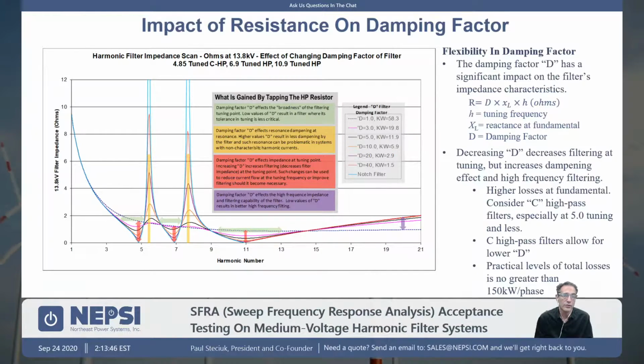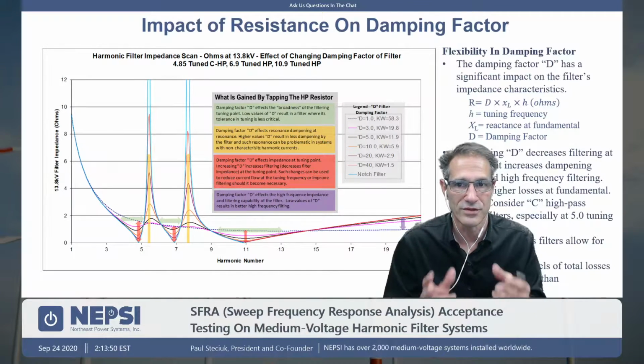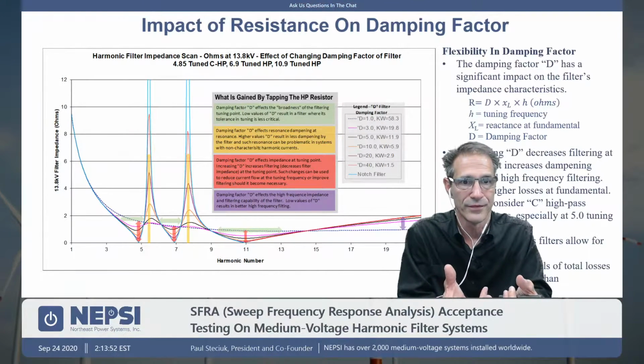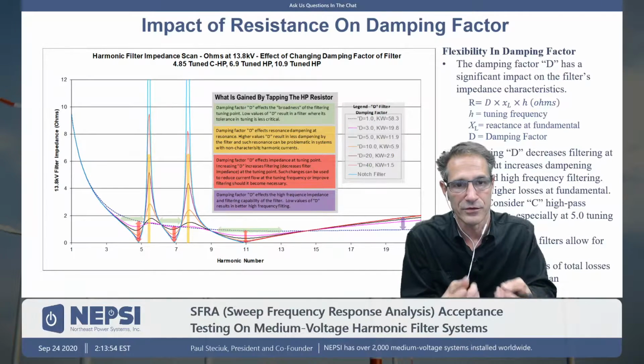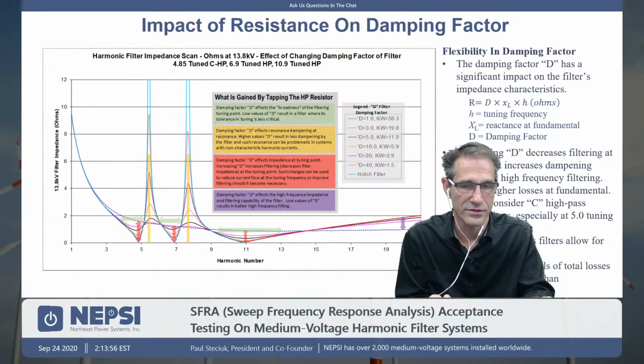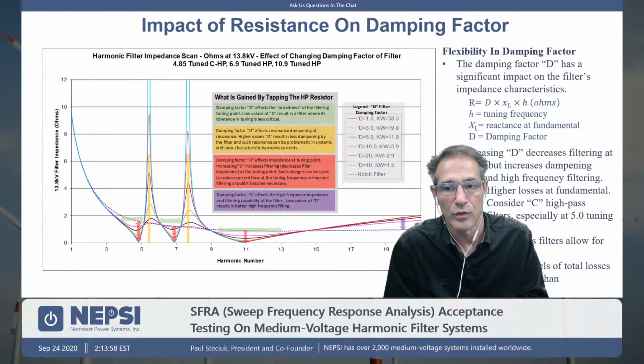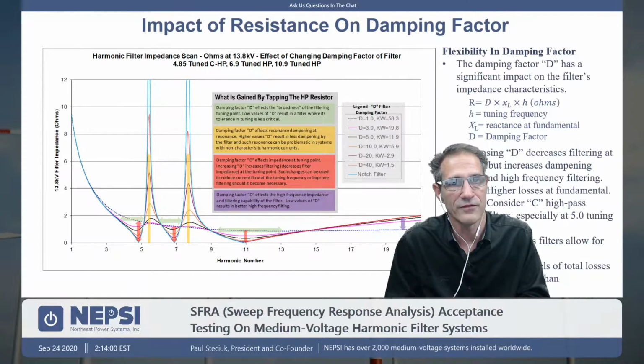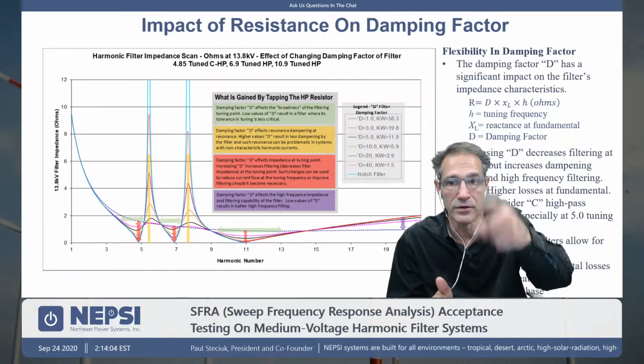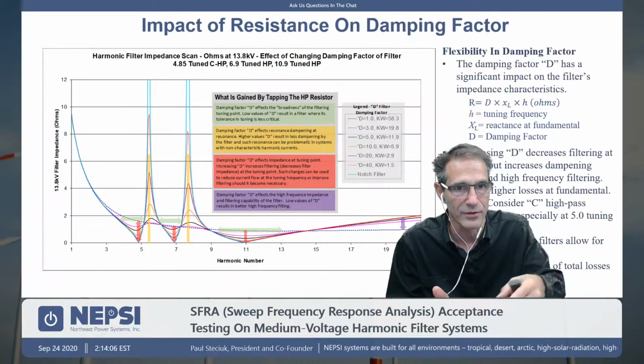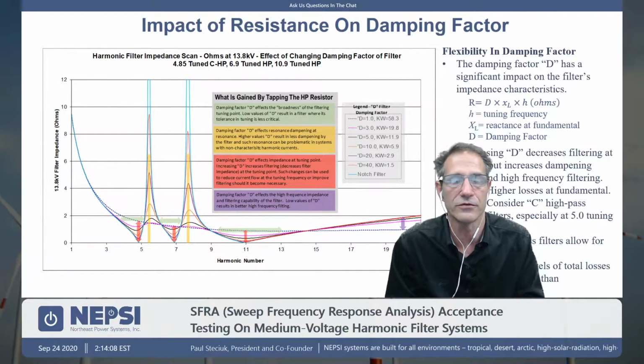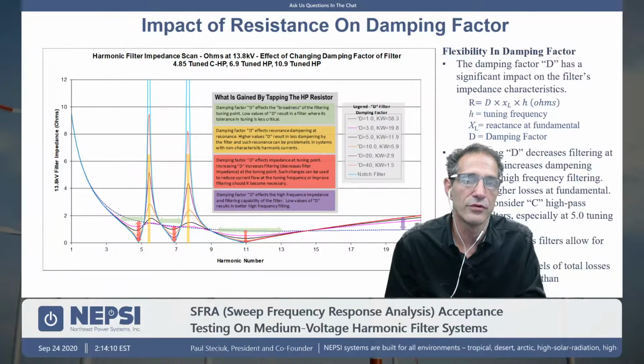And you've got to realize that when we're doing harmonic filter banks and using high-pass resistors, the resistors themselves are cold. The reality is that there's a cold resistance value and a hot resistance value. During the test, we'll come up with a test for cold resistance first, and we'll get a sharper profile. It's not as damped, in other words, it's a sharper profile harmonic filter. And then we will do a hot resistance value.